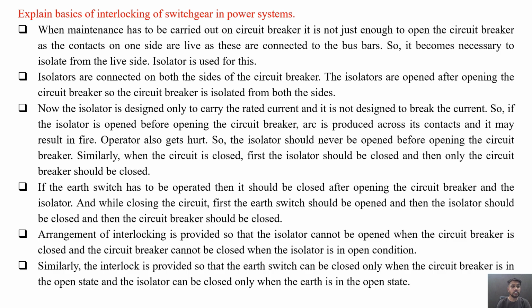Explain basics of interlocking of switchgear in power systems. So when the maintenance has to be carried out on circuit breaker, it is not just enough to open the circuit breaker, as the contacts on one side are live, as these are connected to the bus bars. So it becomes necessary to isolate from the live side also. For this, isolators are used. Isolators are connected on either side, that is both the sides of the circuit breaker. The isolators are opened after the opening of the circuit breaker. So the circuit breaker is isolated from both the sides.